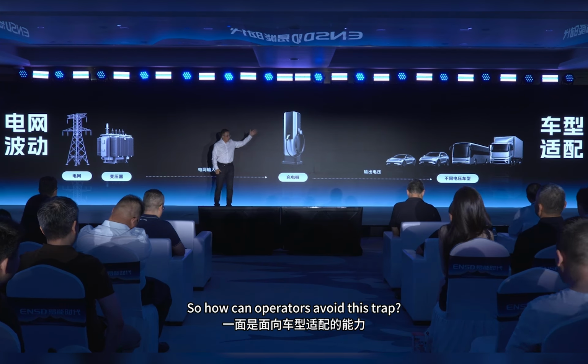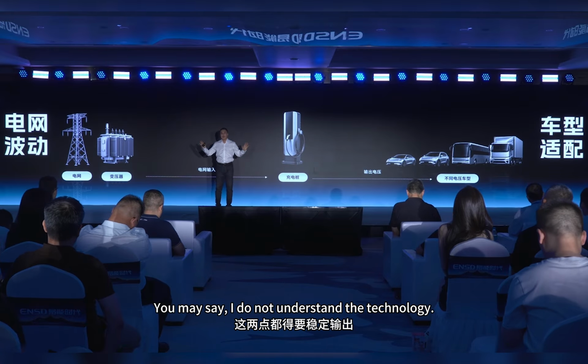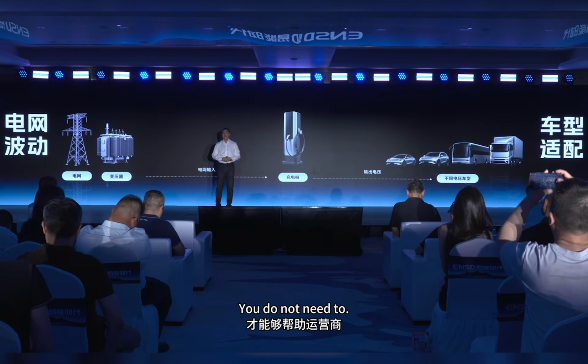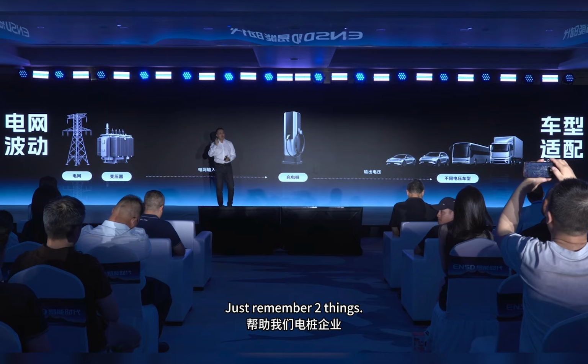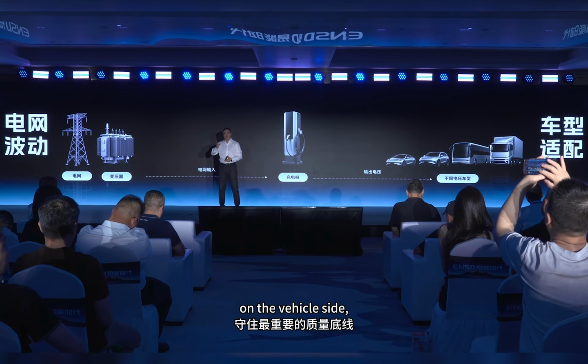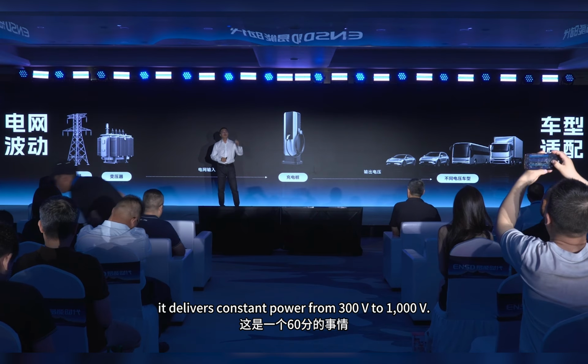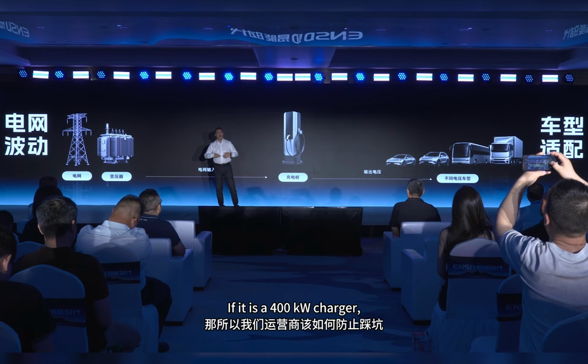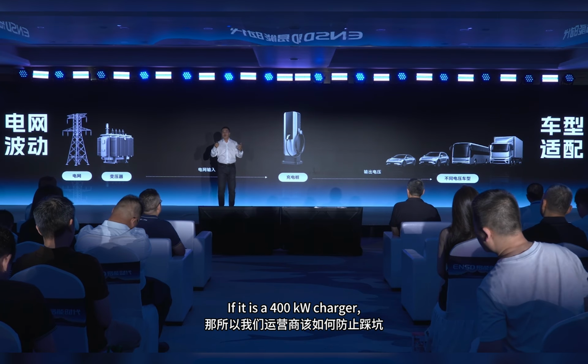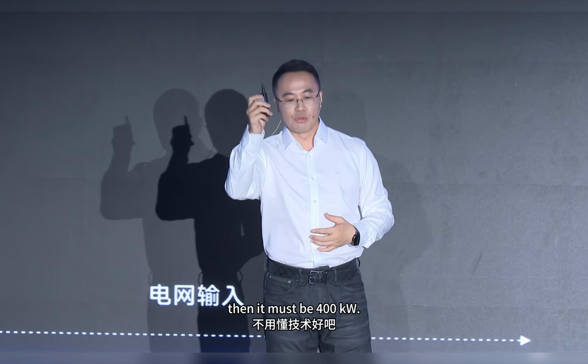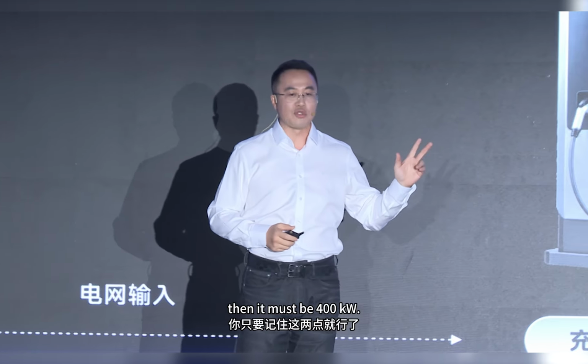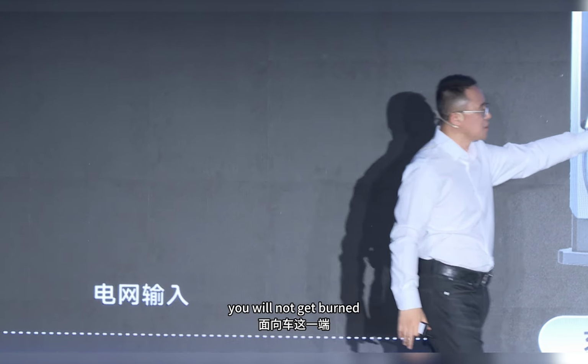So how can operators avoid this trap? You may say, I do not understand the technology. You do not need to. Just remember two things. First, on the vehicle side, require that under high temperatures, if it is a 400 kilowatt charger, it delivers constant power from 300 volts to 1000 volts. Then it must be 400 kilowatts. If you insist on that, you will not get burned.